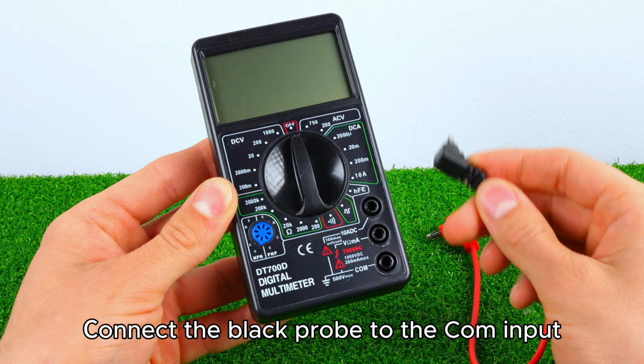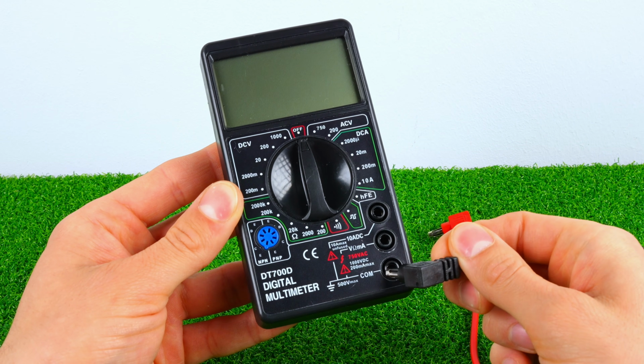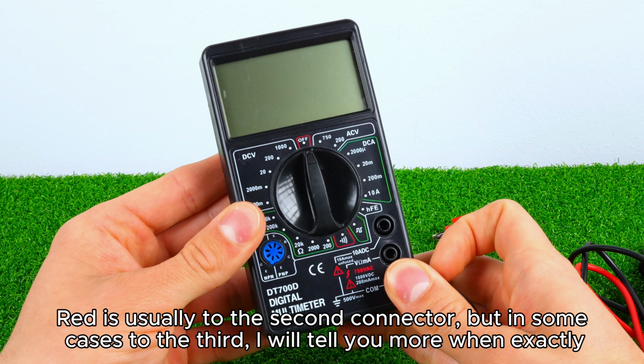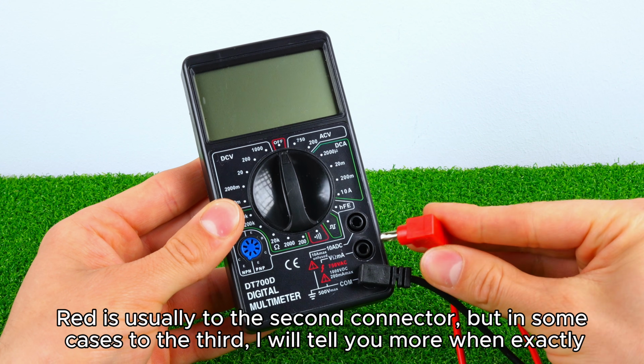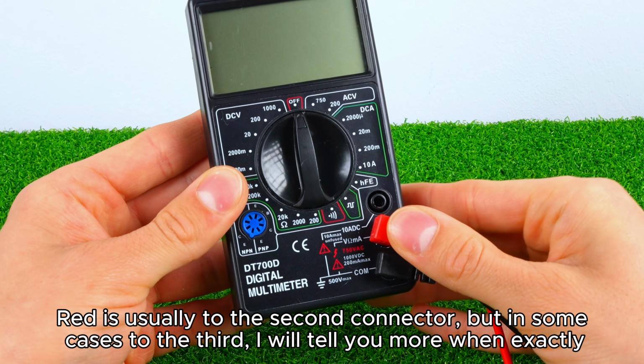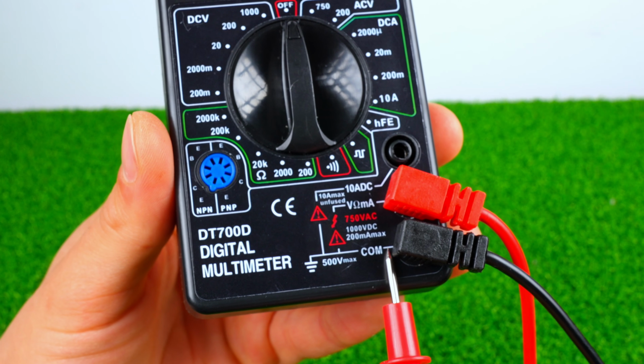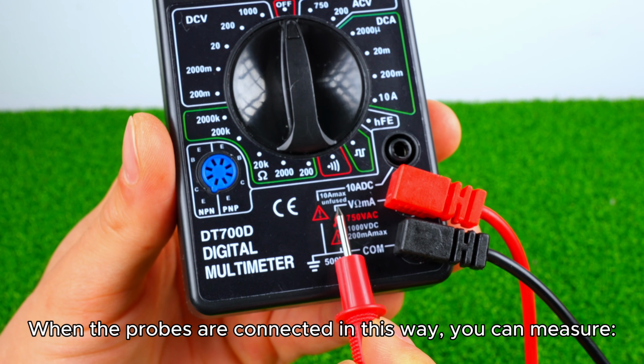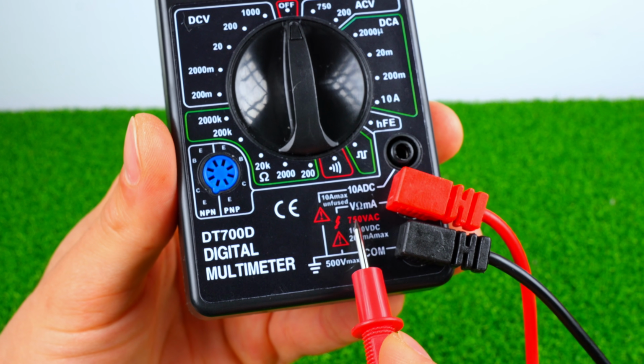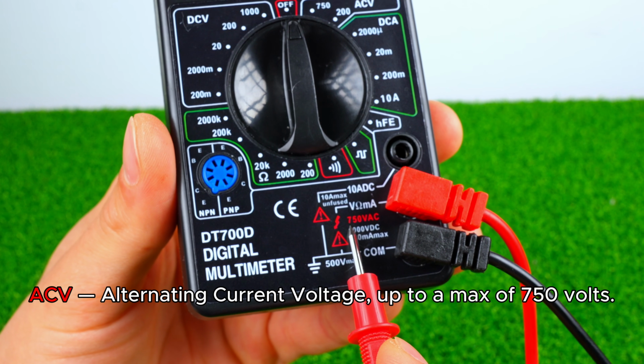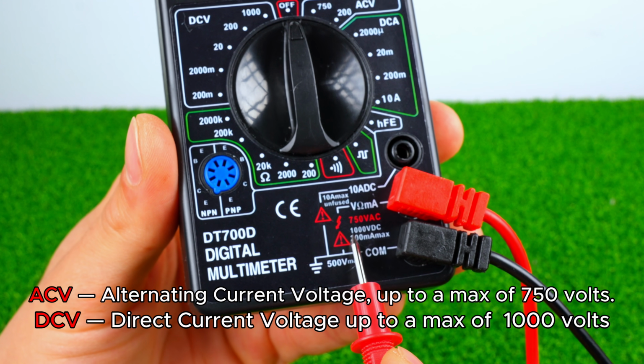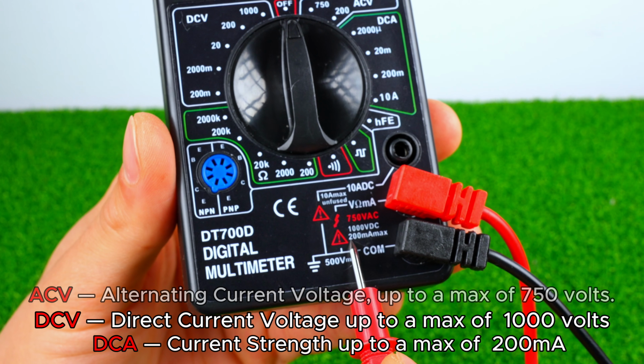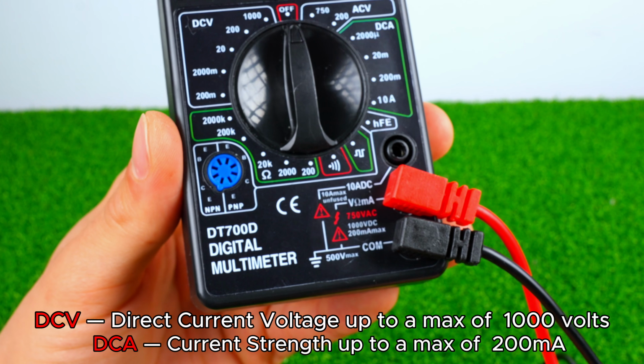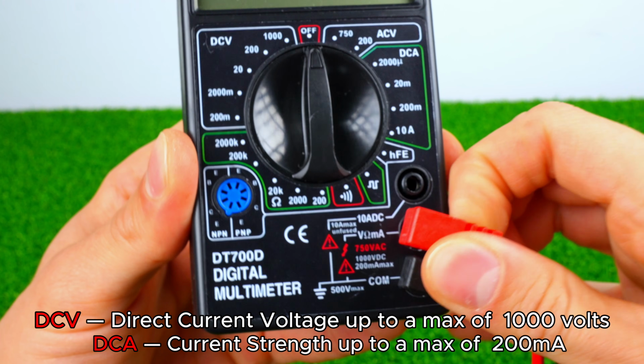Connect the black probe to the COM input. Red is usually to the second connector, but in some cases, to the third. I will tell you more when exactly. When the probes are connected this way, you can measure ACV, a max of 750 volts; DCV, up to a max of 1000 volts; DCA, up to a max of 200 milliamperes.